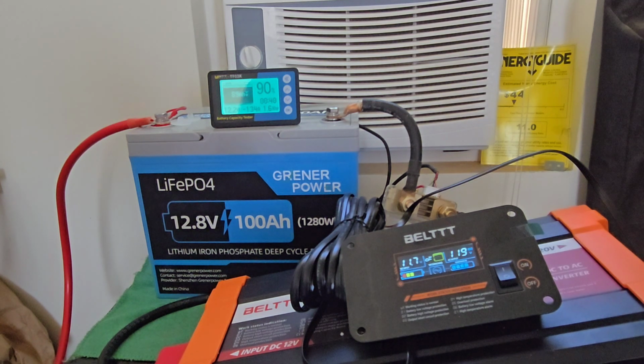All right, charge performance. Recommended charge current is 20 amps - that's what I did charge it at. Maximum charge current is 100 amps. Recommended charge voltage is 14.6 volts, and that's what I charged it at. The BMS cutoff voltage is less than 15.2 volts, or 3.8 volts per cell. Maximum batteries in connection: 4 parallel, 4 series. That's pretty standard with all LiFePO4 batteries.